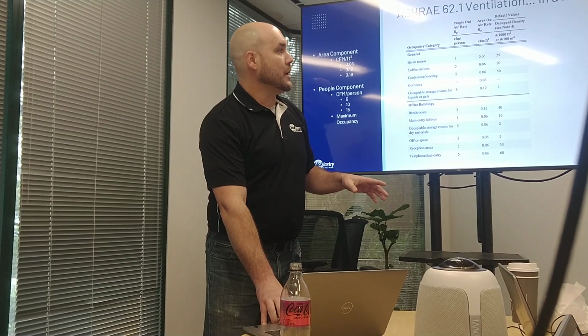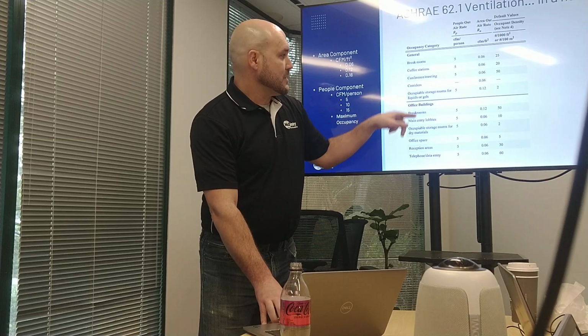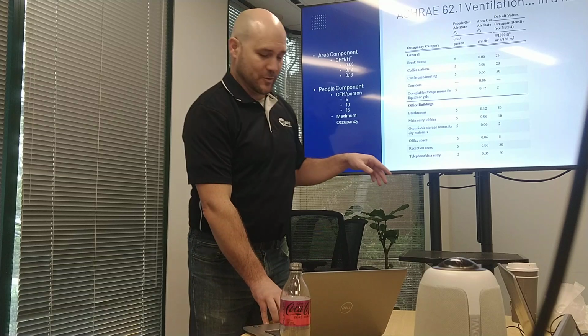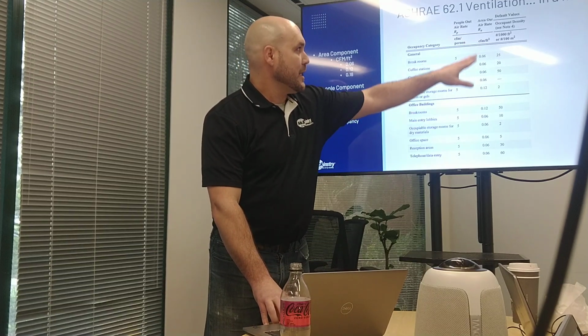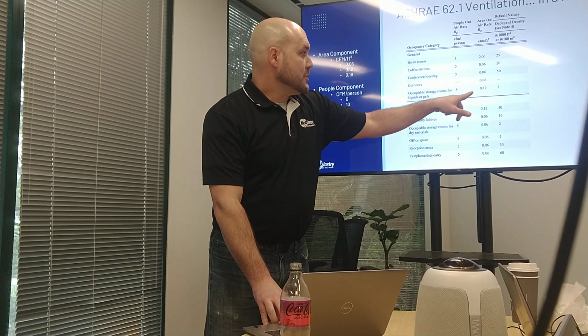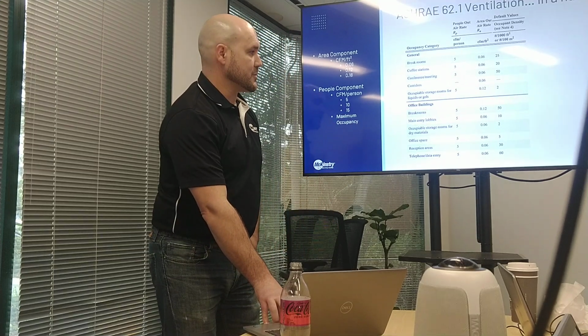If you're sedentary, like in an auditorium versus a conference room, it's probably going to be 5 CFM per person because people are just sitting down. If it's a manufacturing area where people are on their feet and moving around, it might be 10, might be 15. Although the density, the maximum occupancy, how many people are in that space, is going to be highly variable. So this is a look at the chart that's in standard 62.1. You can see CFM per person for different types of spaces, and this is only a small snippet. There's a whole lot more space types, but yes, the area rate for storage rooms is 0.12, even while the people component is still 5 CFM per person.